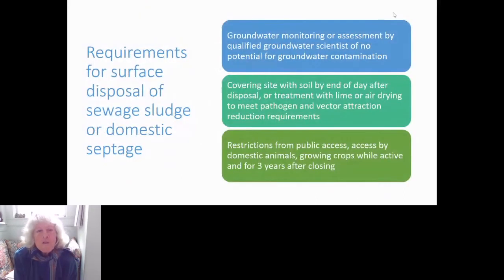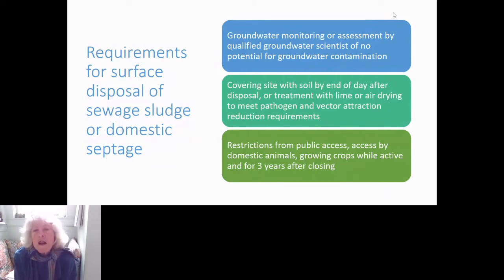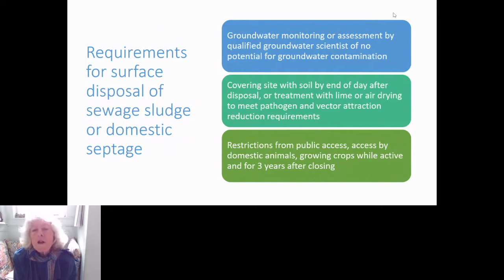For surface disposal, the primary requirement if you place sludge on land for disposal is to do groundwater monitoring, or to get an assessment by a qualified groundwater scientist that there's no potential for groundwater contamination. If it's several hundred feet to groundwater, there wouldn't be a concern. If it's five or ten feet, there would be a concern, and you'd need monitoring, or you'd need to avoid surface disposal or line the site.